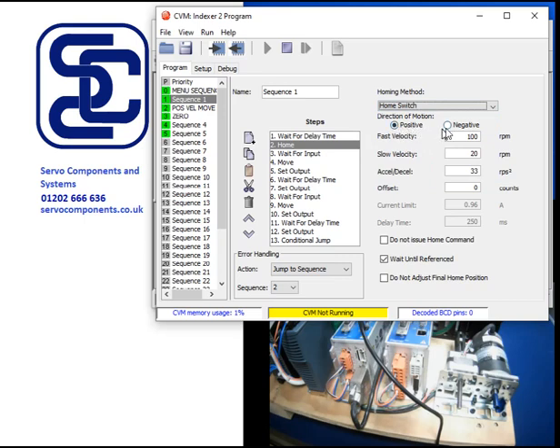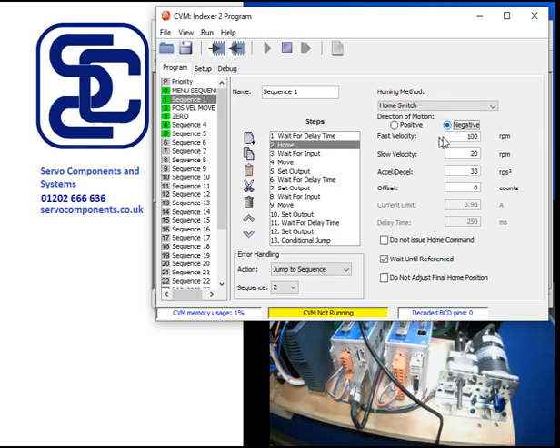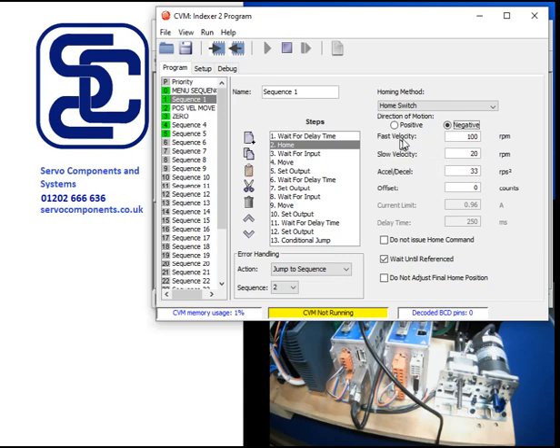So again, let's assume that we have to move backwards to the home switch to get to the switch. So I'm going to click negative move here and you'll see we've got a fast velocity and a slow velocity. So what it actually does, it will move to the switch at a fast velocity, see the switch and then move off the switch at a low velocity.